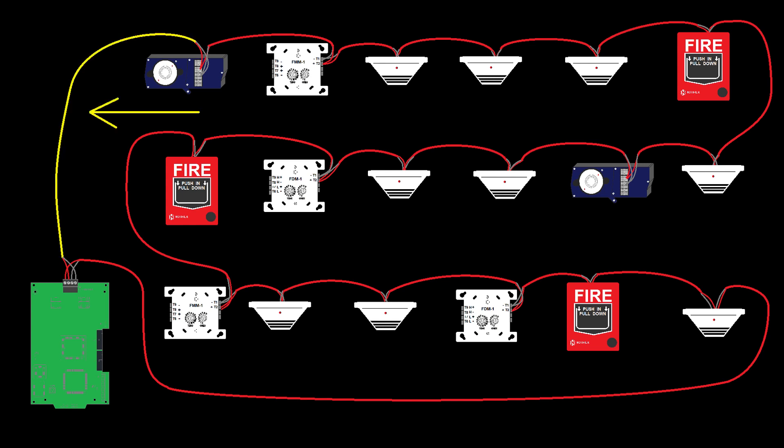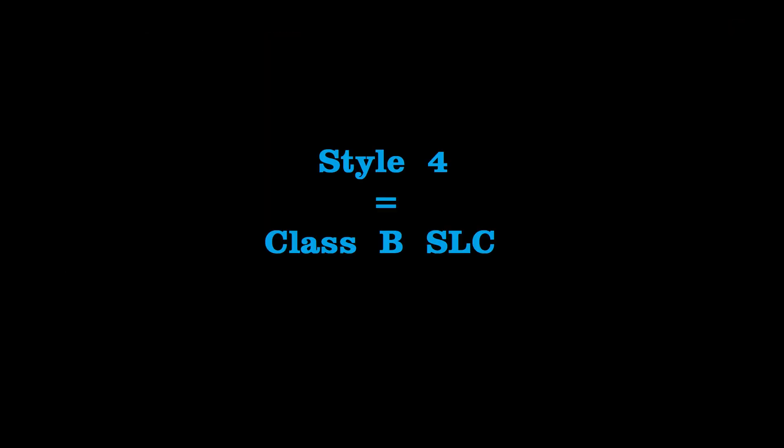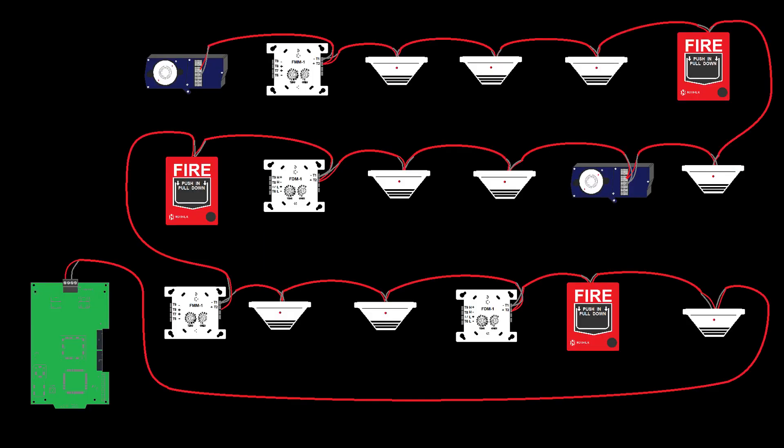We're going to remove this return leg of the circuit. Now we have an example of a style 4 or Class B loop. It's style 4 because it does not return back to the panel after the last device. If I had a single wire open at any point in this circuit, any device after that point on the loop would no longer be able to communicate with the panel.